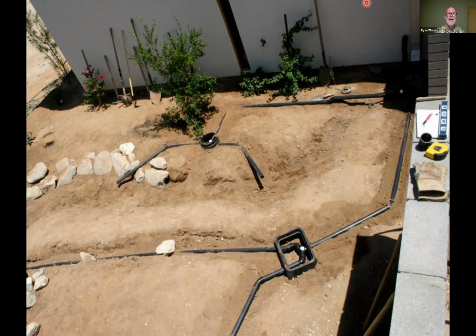And here's a good way of showing this. When you're laying that pipe, notice there's a little bit of drop right here. The more that we can get that water to drop and keep moving through, the better, but we have to keep a 1/4 inch per foot. So that's important, a 1/4 inch per foot on your branch drain pipe. And that's the same as your sewer pipe.